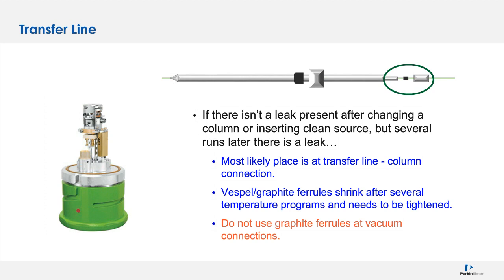The septa on your GC could be leaking. Remember, it's unlike other detectors: the leak isn't going out, it's going into the system because you have a vacuum pulling on it. Leaks downline at the cylinder, no, they will go out. The vacuum is not a factor there. But leaks in the instrument, I would say from the injector port on, you can pick up with a leak detector because it's being pulled in. So that's why we use the dust off, because it's pulling it in. But remember the injector port when leak checking as well.